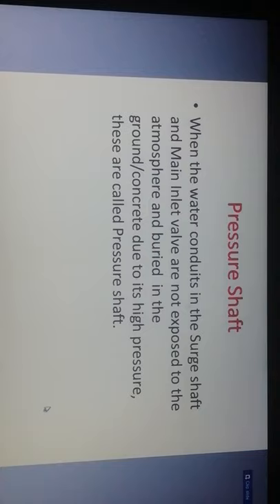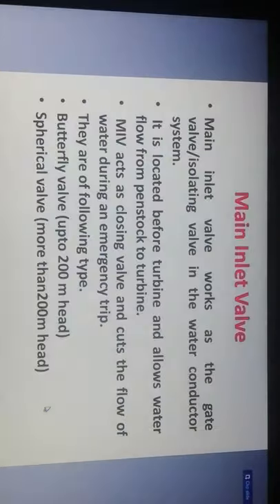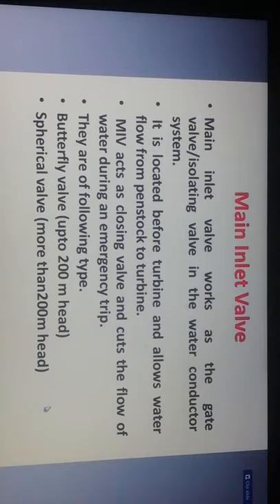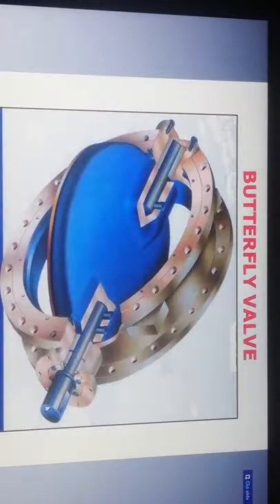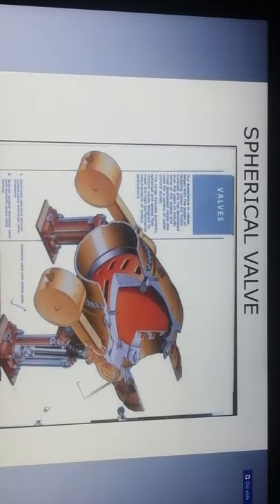A pressure shaft is where water conduits are not exposed to the atmosphere and are buried in the ground or concrete due to high pressure. The main inlet valve works as a gate valve/isolating valve in the water conductor system. It is located before the turbine and allows water flow from the penstock to the turbine. The main inlet valve acts as a closing valve and cuts the flow of water during emergency. Types include butterfly valve for up to 200 meter head and spherical valve for more than 200 meter head.